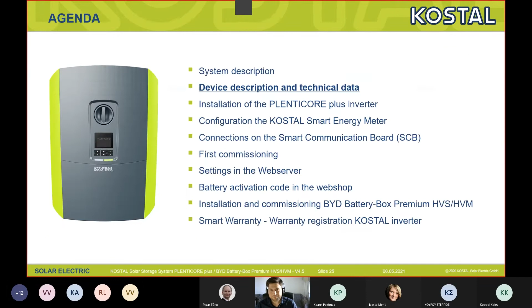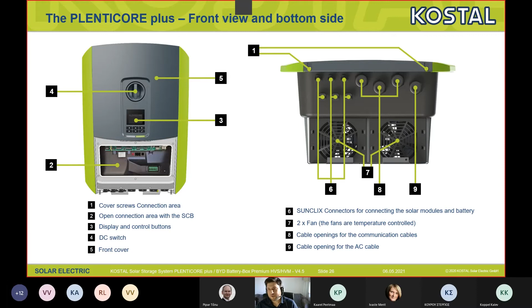Here you can see the front view and the bottom side of the Plenticore Plus. Number one is the cover screws, the connection area. Number two is the open connection area, and you see part of the smart communication board. It's the only area that you can come in contact with from inside the inverter. Number three is the display. Number four, the DC switch. And number five is the front view cover. Also, you can see the bottom side where we have the fans, the DC connection, and the cable openings for the communication cables and for the AC cables.